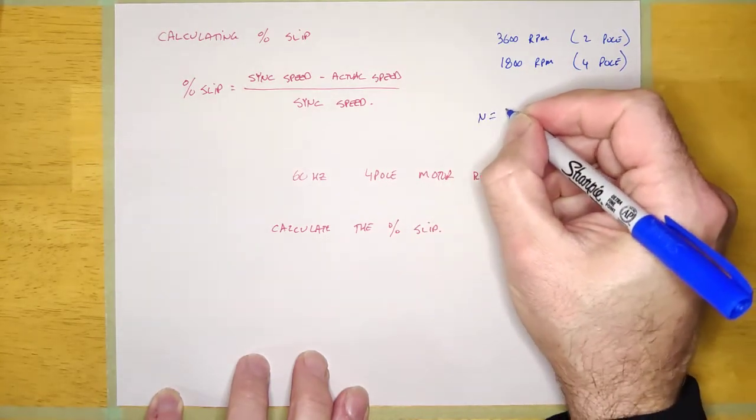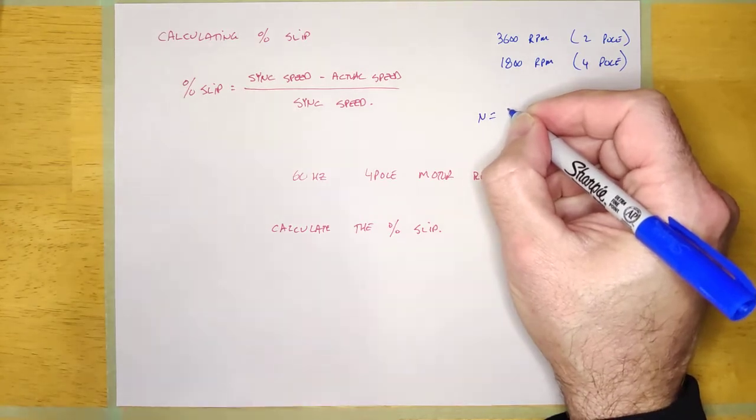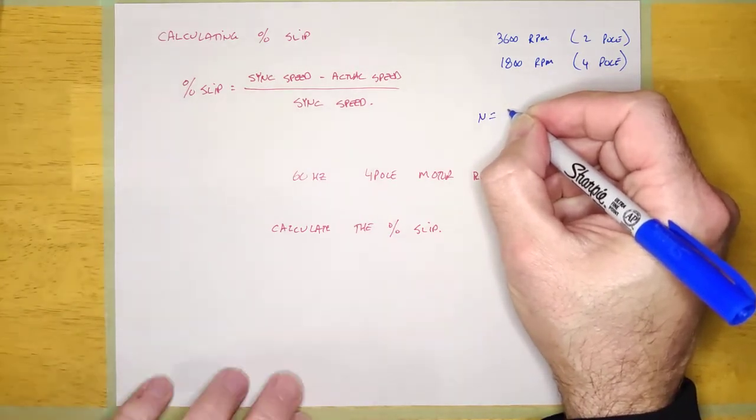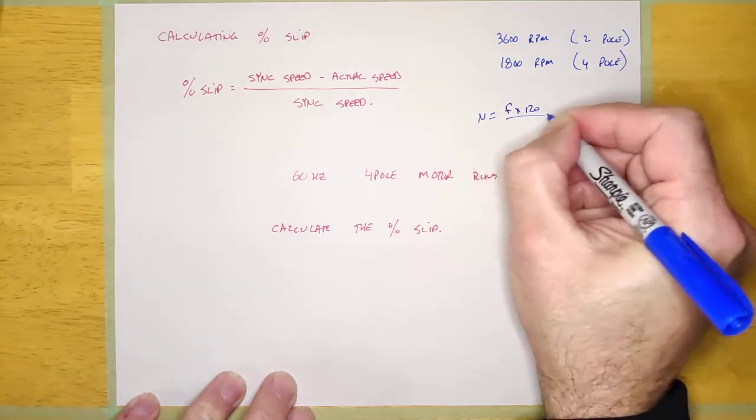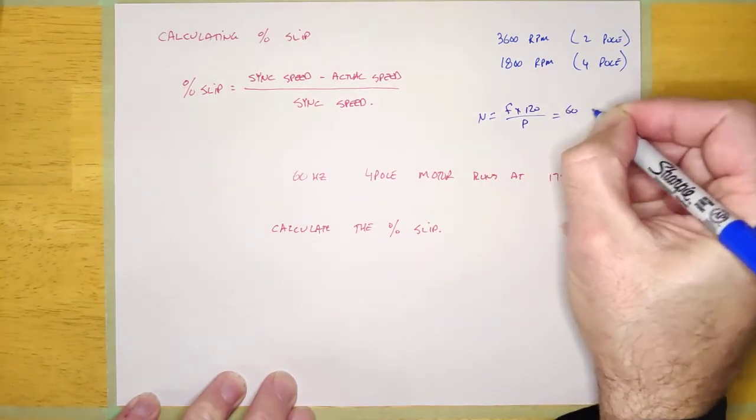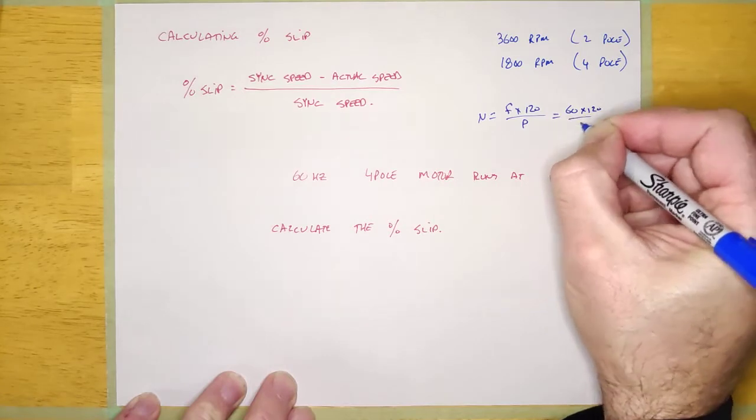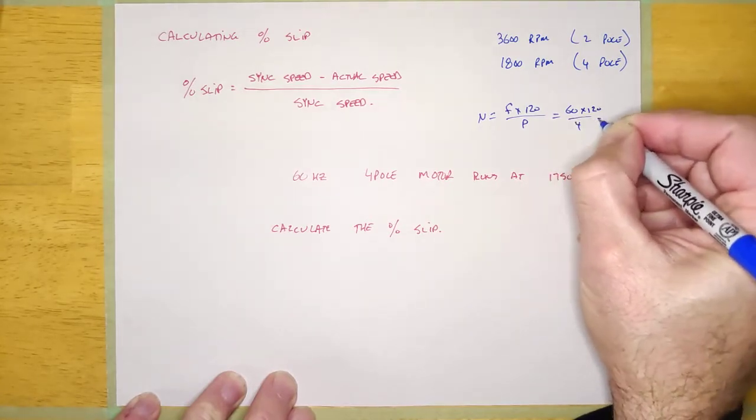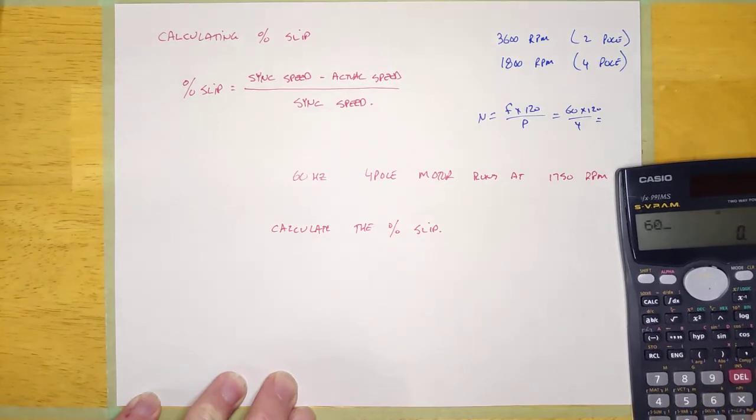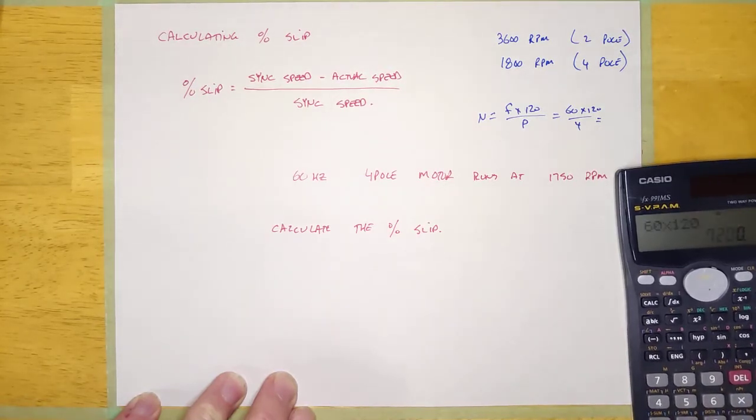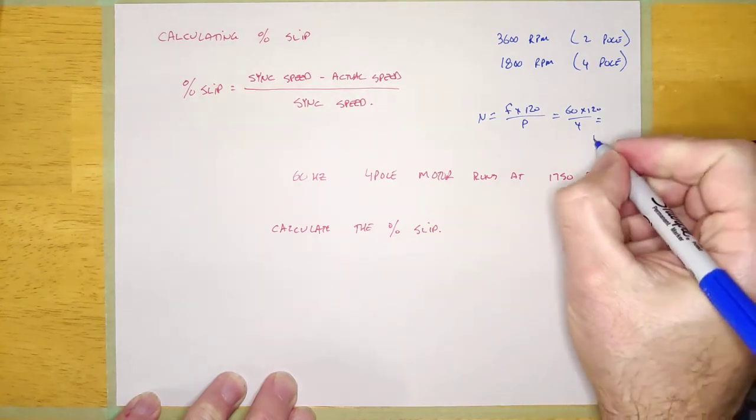N is equal to, what is it again? I can't even remember the formula right here. F times 120 over P. And so it's 60 times 120 over 4, and you can see that if I calculate that, 60 times 120 equals divided by 4 equals 1,800 RPM.